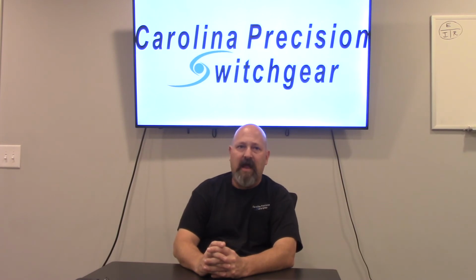You also have a phase to ground fault, which is referred to as a ground fault. And a ground fault is when a phase has gone to ground and doesn't necessarily involve the other phases. However, you really will only have ground fault protection, and a breaker will only trip on a ground fault if it has that function available. So if you have a breaker that does not have ground fault and it experiences a ground fault, it may not trip at all. So something to consider.